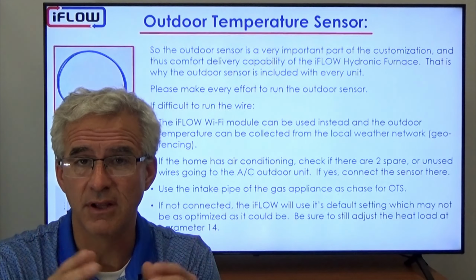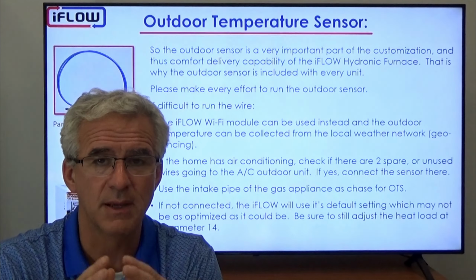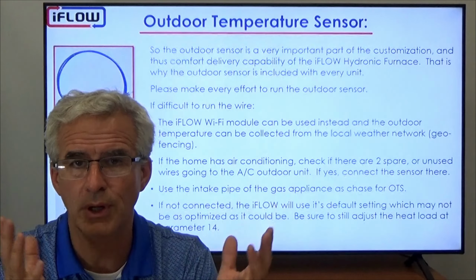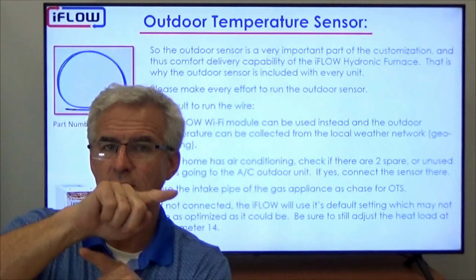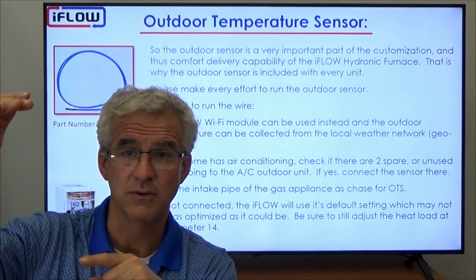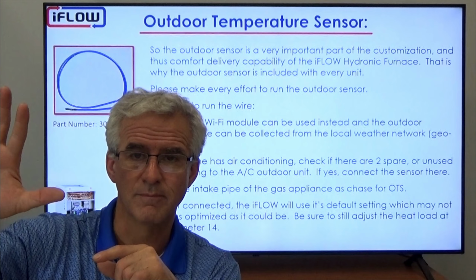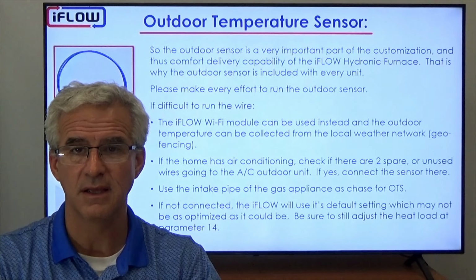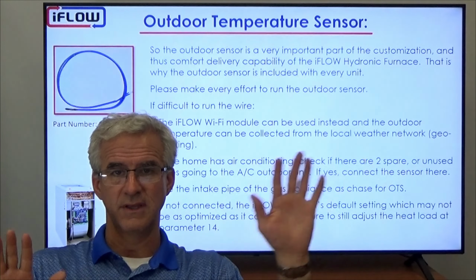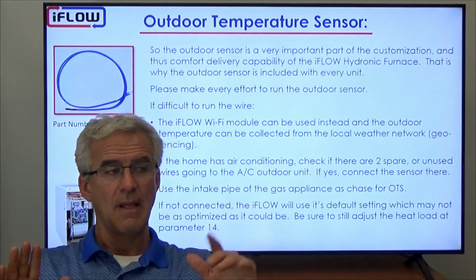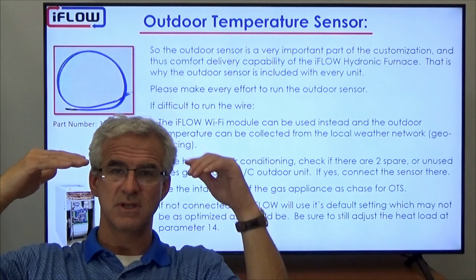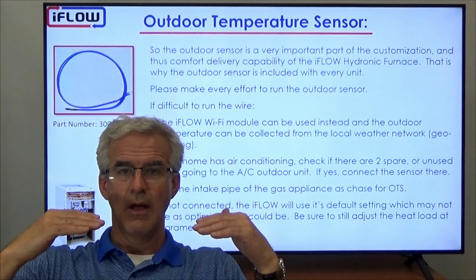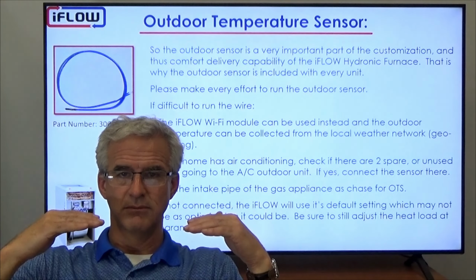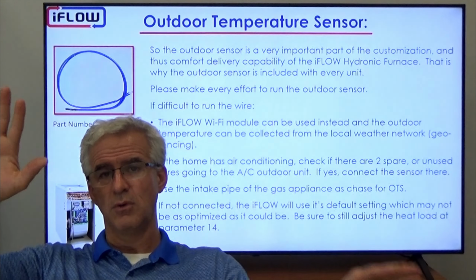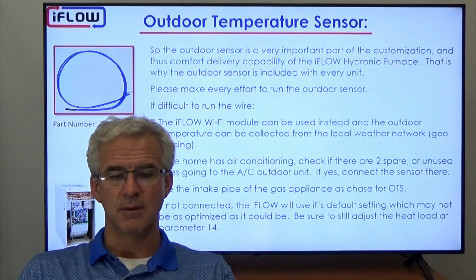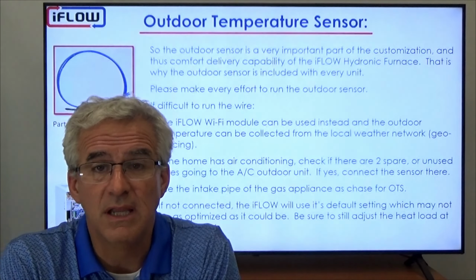If we're not with a Navien, if we're with a combi boiler, let's say an NTI boiler, a Viessmann boiler, an IBC boiler, a Triangle Tube boiler, or Lochinvar, whatever boiler you're using, you want to have the outdoor sensor connected to that boiler or combi boiler so that it will also modulate and have the outdoor reset set up on the boiler. But then you also want to hook the outdoor reset to the iFLOW as well, so that the iFLOW will be looking at the outdoor temperature and adjusting its delivery based on it, but the boiler will also have its own outdoor temperature sensor connected, so it's going to be doing the same thing. So as it gets colder, both will ramp up. As it gets milder, both will ramp down. So even if you have it on the boiler, you also need it on the iFLOW. You need it on both appliances to get the performance that we need on the iFLOW.